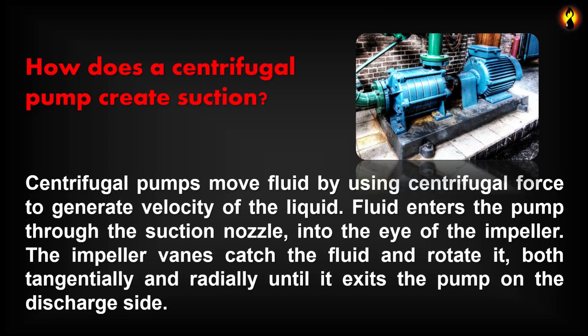How does a centrifugal pump create suction? Centrifugal pumps move fluid by using centrifugal force to generate velocity of the liquid. Fluid enters the pump through the suction nozzle into the eye of the impeller. The impeller vanes catch the fluid and rotate it both tangentially and radially until it exits the pump on the discharge side.